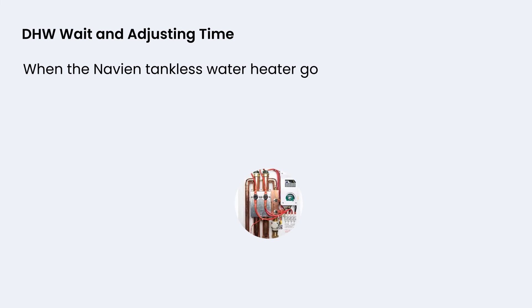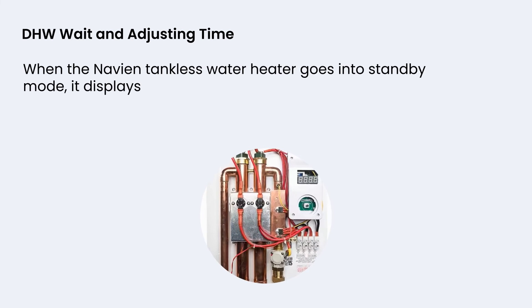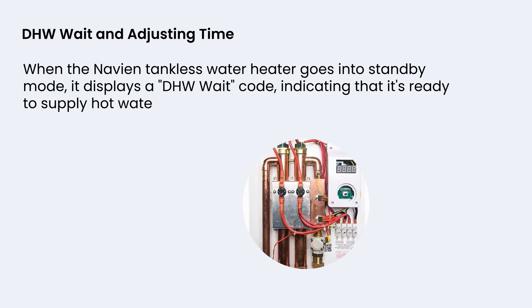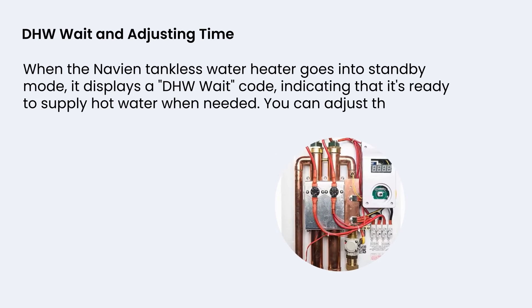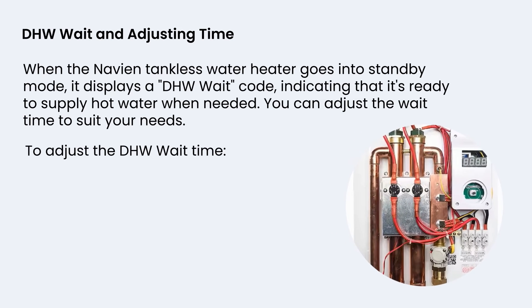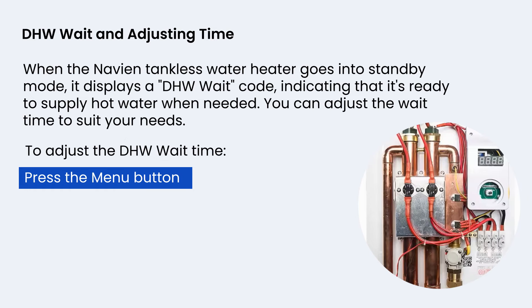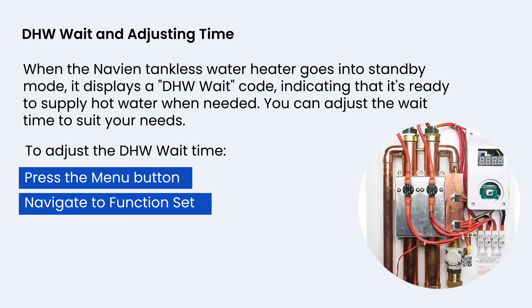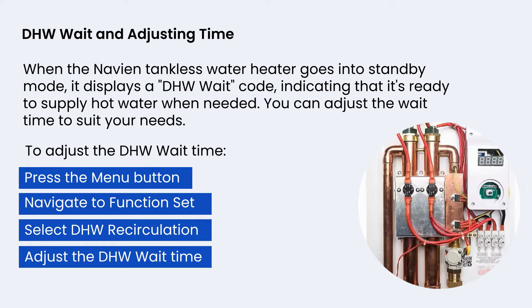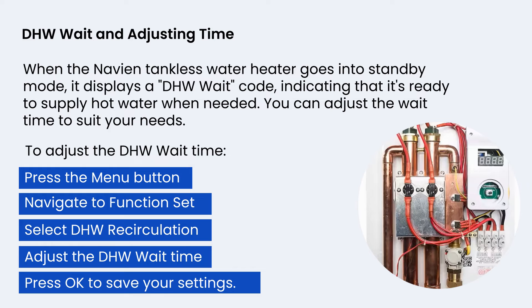When the Navien tankless water heater goes into standby mode, it displays a DHW wait code, indicating that it's ready to supply hot water when needed. You can adjust the wait time to suit your needs. To adjust the DHW wait time: press the menu button, navigate to Function Set, select DHW Recirculation, adjust the DHW wait time, then press OK to save your settings.